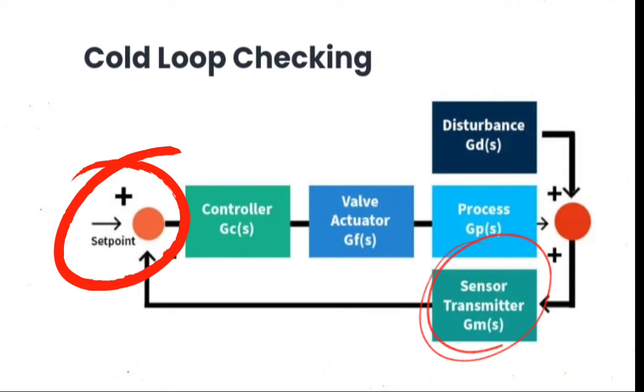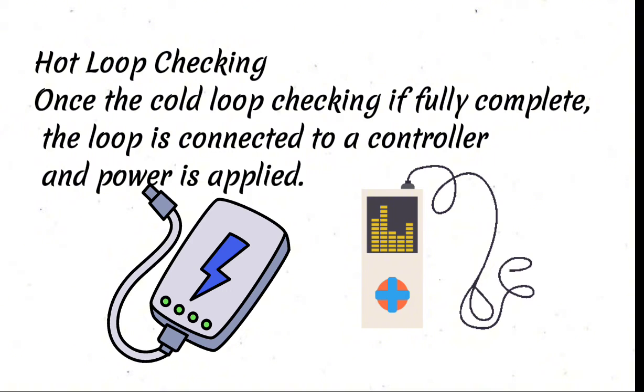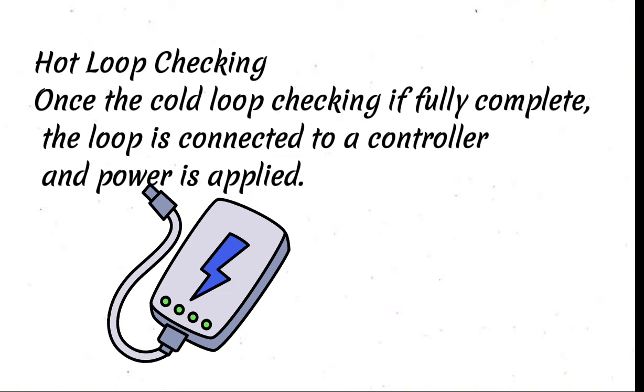Continuity is tested for each of the branch cables to verify the continuity between the controllers. Hot loop checking is performed once cold loop checking is fully complete. The loop is connected to a controller and power is applied.